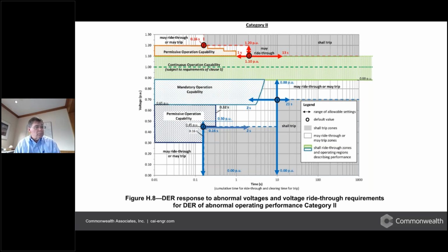And one thing to point out here is, you look at the difference between shall trip and continuous operation. Well, if the equipment is rated to handle the condition, then you don't have to be right on the line. You can be in an area that provides better ride-through capability. Sometimes it's interpreted as, I need to be exactly on these lines, but you have to base that decision, setting your levels, on equipment ratings.